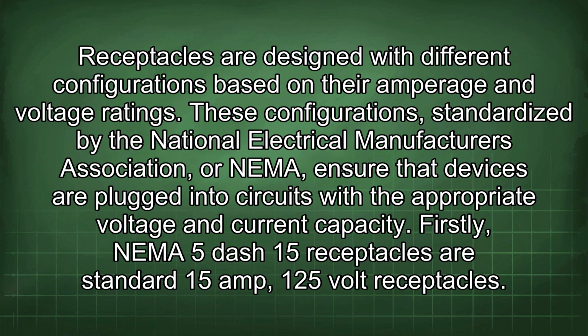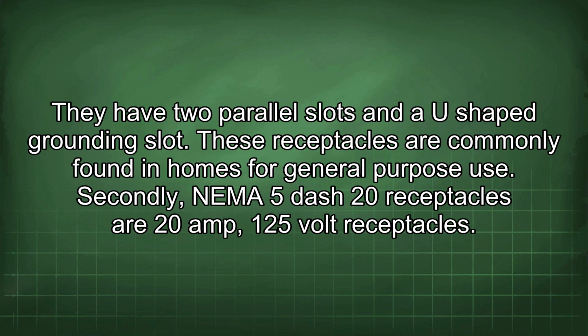Receptacles are designed with different configurations based on their amperage and voltage ratings. These configurations, standardized by the National Electrical Manufacturers Association, or NEMA, ensure that devices are plugged into circuits with the appropriate voltage and current capacity. Firstly, NEMA 5-15 receptacles are standard 15 amp 125 volt receptacles. They have two parallel slots and a U-shaped grounding slot. These receptacles are commonly found in homes for general purpose use.